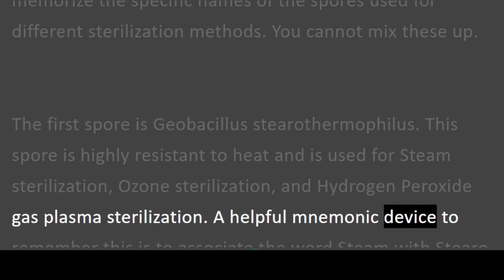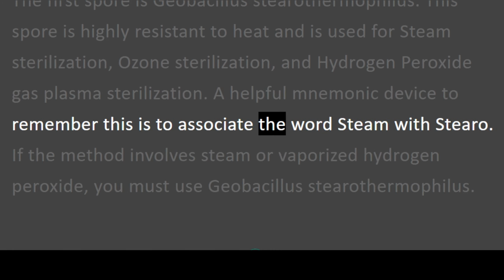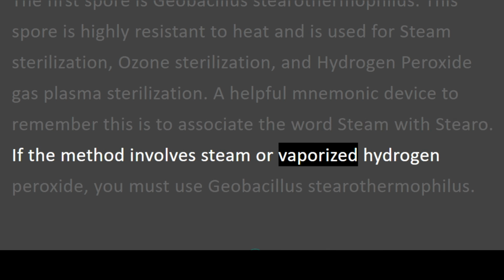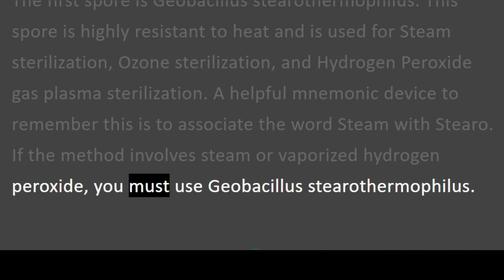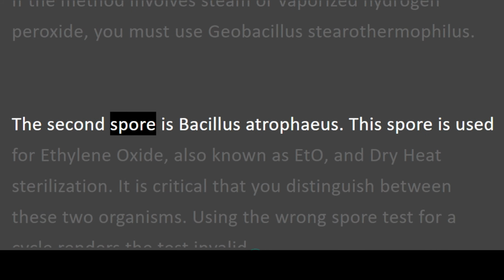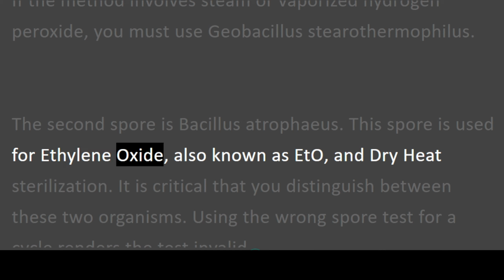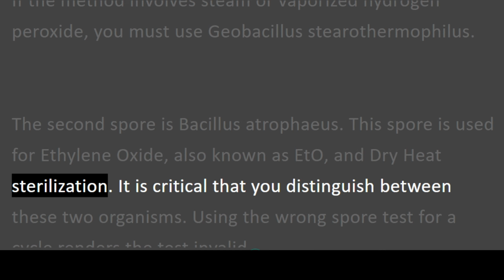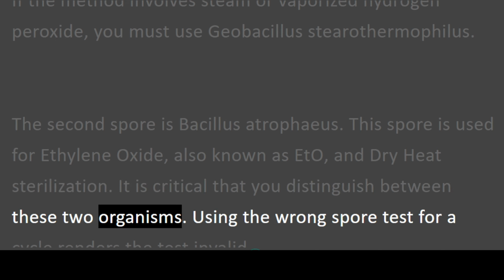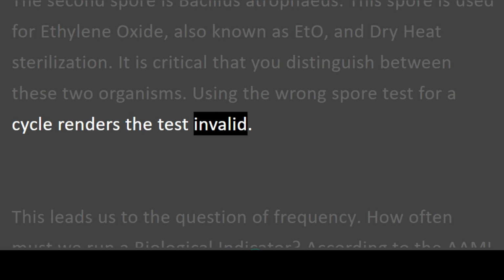A helpful mnemonic device to remember this is to associate the word steam with Stearo. If the method involves steam or vaporized hydrogen peroxide, you must use Geobacillus stearothermophilus. The second spore is Bacillus atrophaeus. This spore is used for ethylene oxide, also known as ETO, and dry heat sterilization. It is critical that you distinguish between these two organisms. Using the wrong spore test for a cycle renders the test invalid.